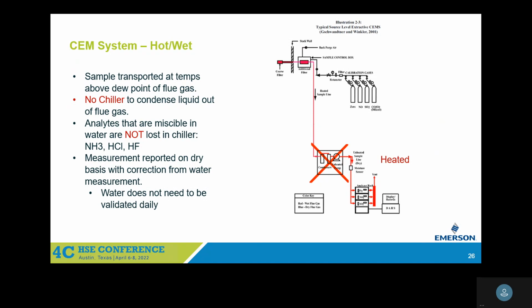So what we've been doing, and I think I mentioned roughly half of all are hot wet systems. That's where we're hot all the way through, all the way through the analyzer itself, and to the plant. These are P&ID diagrams. So there's no chiller, and for analytes such as ammonia in particular, you're not losing everything. You're keeping everything above dew point. The key is that you still need to report a dry basis.